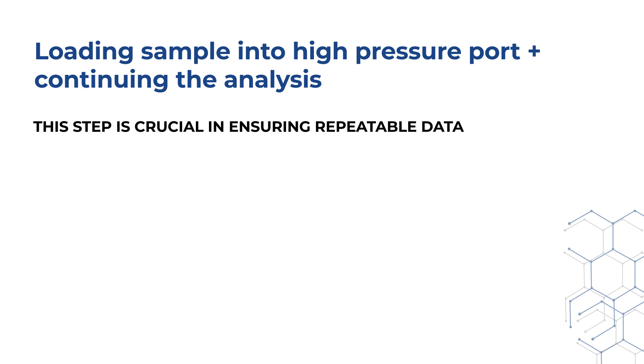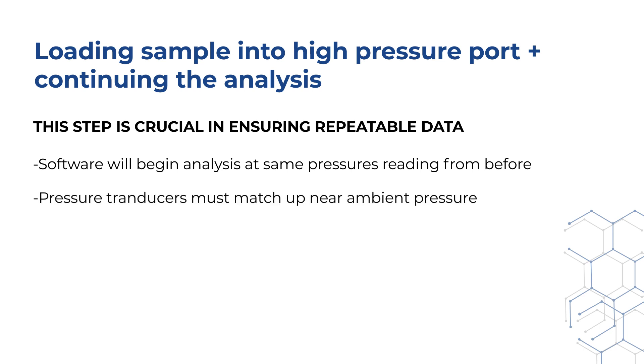The software will start the high-pressure analysis at the same pressure as that last low-pressure point, but we need to make sure that the pressure transducers match up near ambient pressure. The high-pressure system may have just completed an analysis, possibly resulting in some pressure offset at the lower end of the operational range due to hysteresis in the transducer.